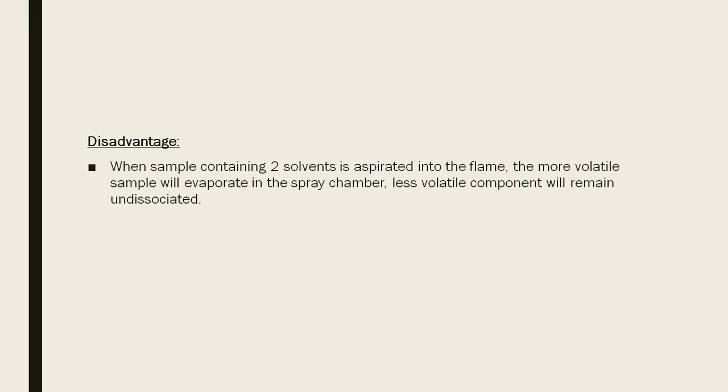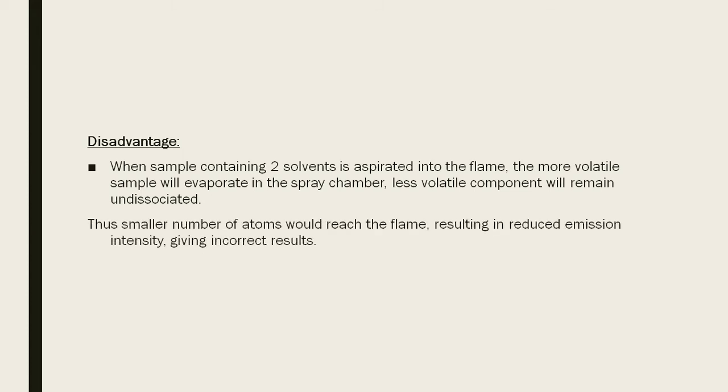Disadvantage: whenever the sample contains two solvents, the more volatile solvent will evaporate in the spray chamber and the less volatile component will remain undissociated. A smaller number of atoms will reach the flame, resulting in reduced emission intensity, giving incorrect results.